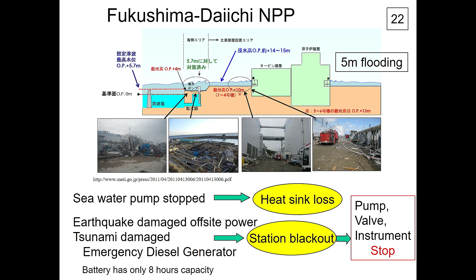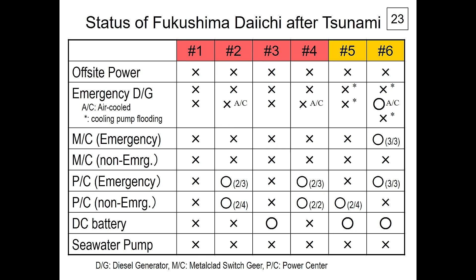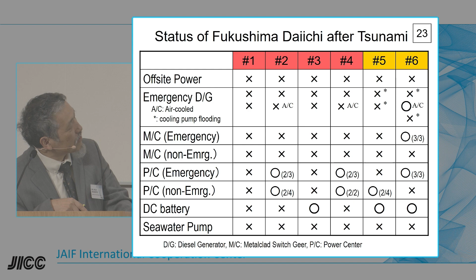This is the biggest issue. So I listed some systems. Offsite power has been lost, and for the emergency DG, diesel generator, emergency power supply, only one air-cooled power supply was available; another power supply was flooded. Another electric transfer system is also somewhat available, but maybe lots of them are down. And DC battery power is available only in Units 3, 5, and 6. In Unit 1, they may have lost everything. This is the worst reactor. Units 2 and 3 also tried to survive during operation. Unit 3 tried to survive on DC battery. But after 3-4 days, the cooling system failed.